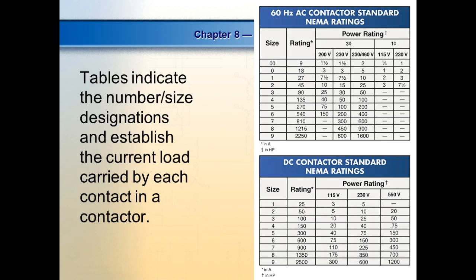So each contactor should have a size rating on it. These are all NEMA, which is National Electrical Manufacturers Association. These are the sizes that they've established for different motor starters. So we have a 00 motor starter. So then once you get to 00, then you come up and you say, okay, what size motor would that handle? Well, size 0 is in AC and a single phase and three phase. So on a size 00, which is what we have, this is the one that we're going to use. Then that says, okay.